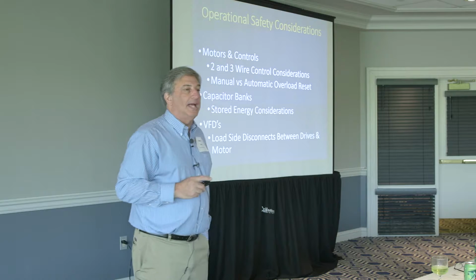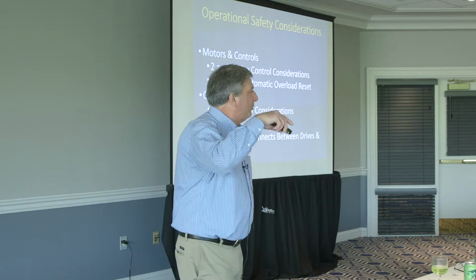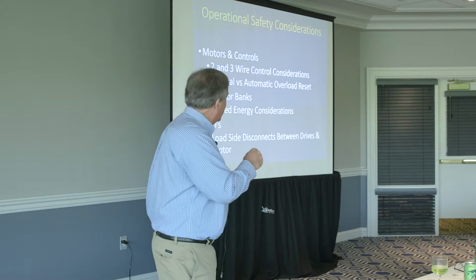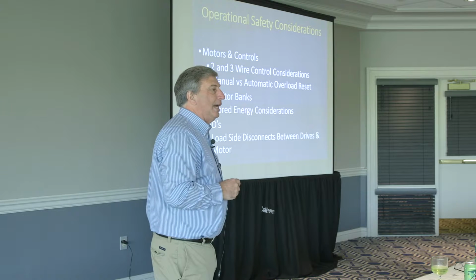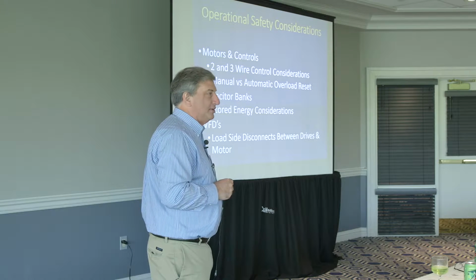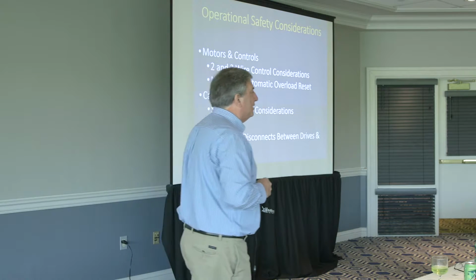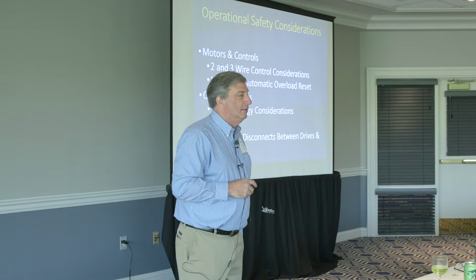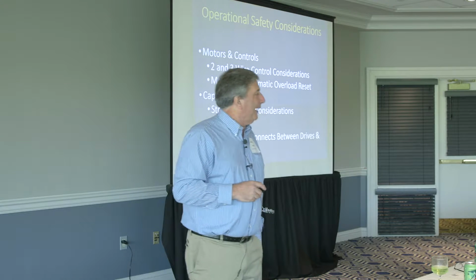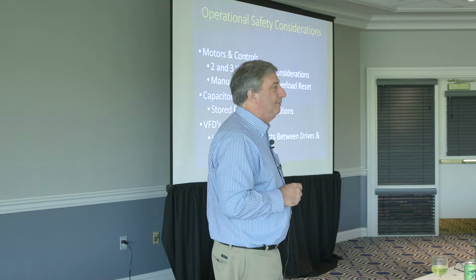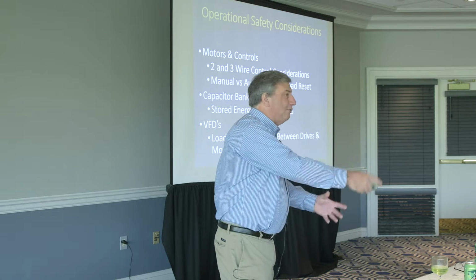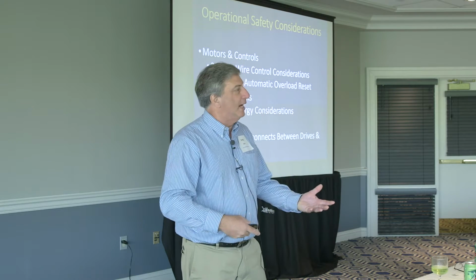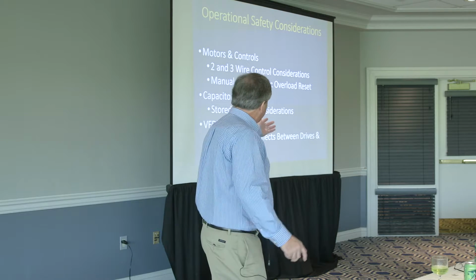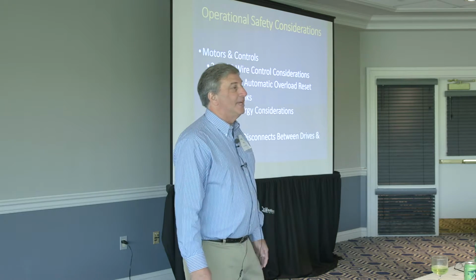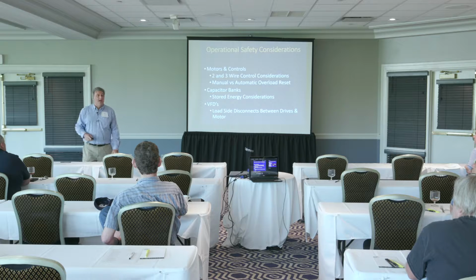And the reason I say that is because I do a number of these different things where somebody gets hurt when they didn't realize there were automatic overload resets. They assumed because the equipment was not running that the power had been locked out and tagged out. They were messing around with shafts or gear trains or something when that automatic overload reset turned the system back on, lost fingers, hands, arms, etc.